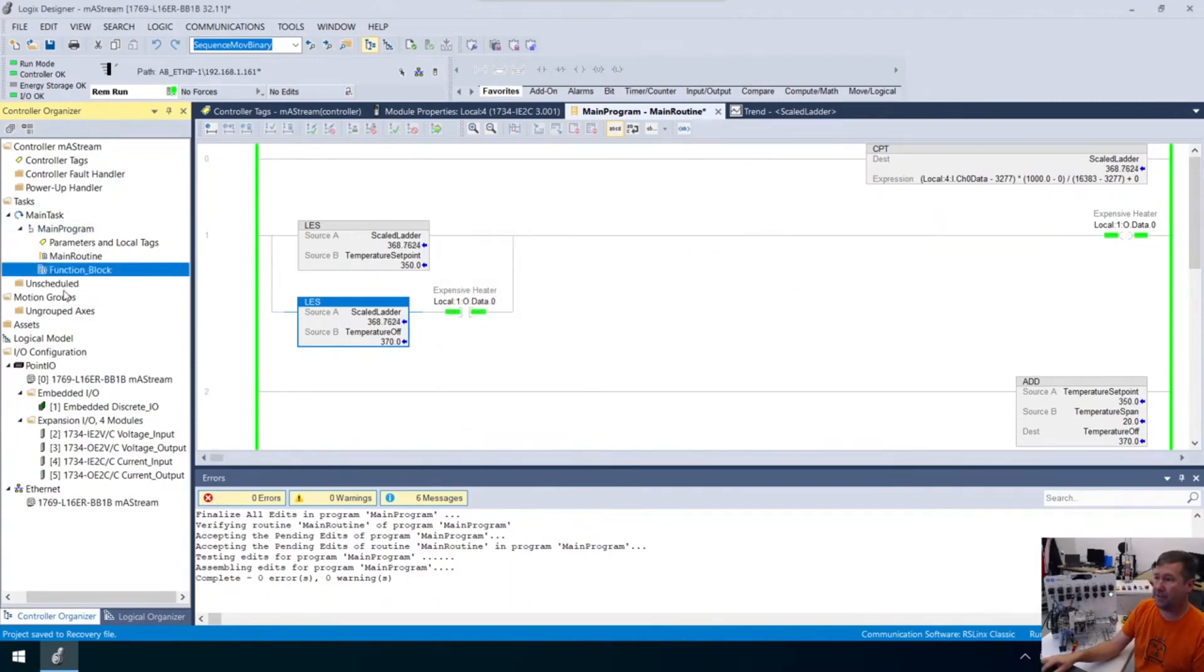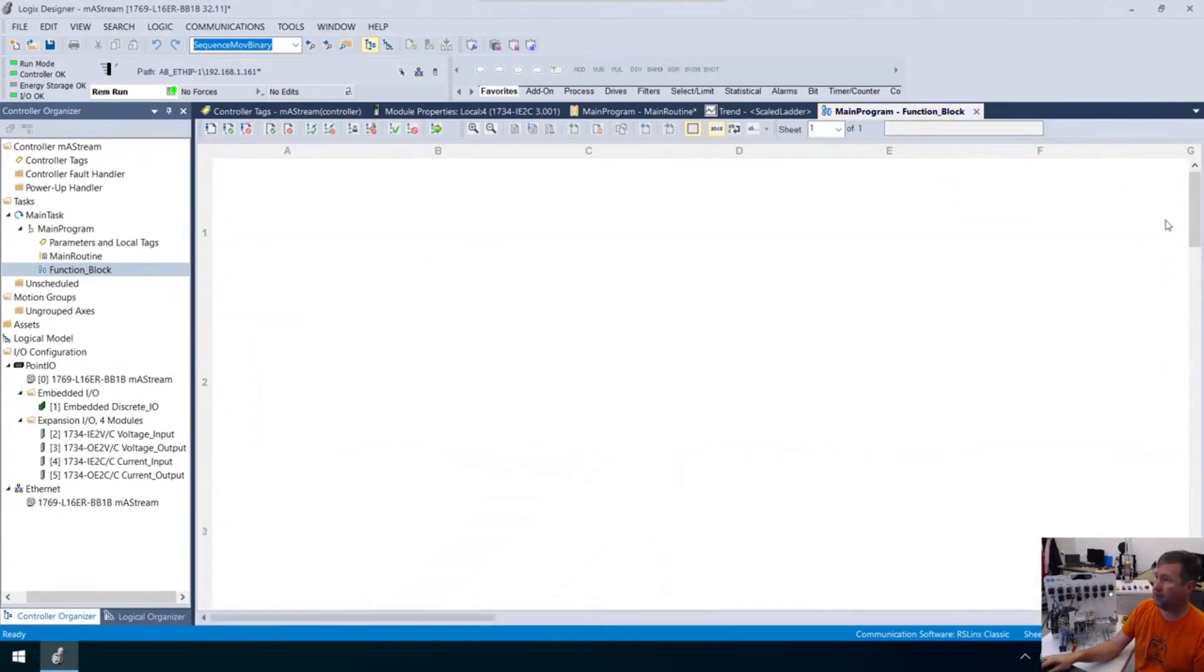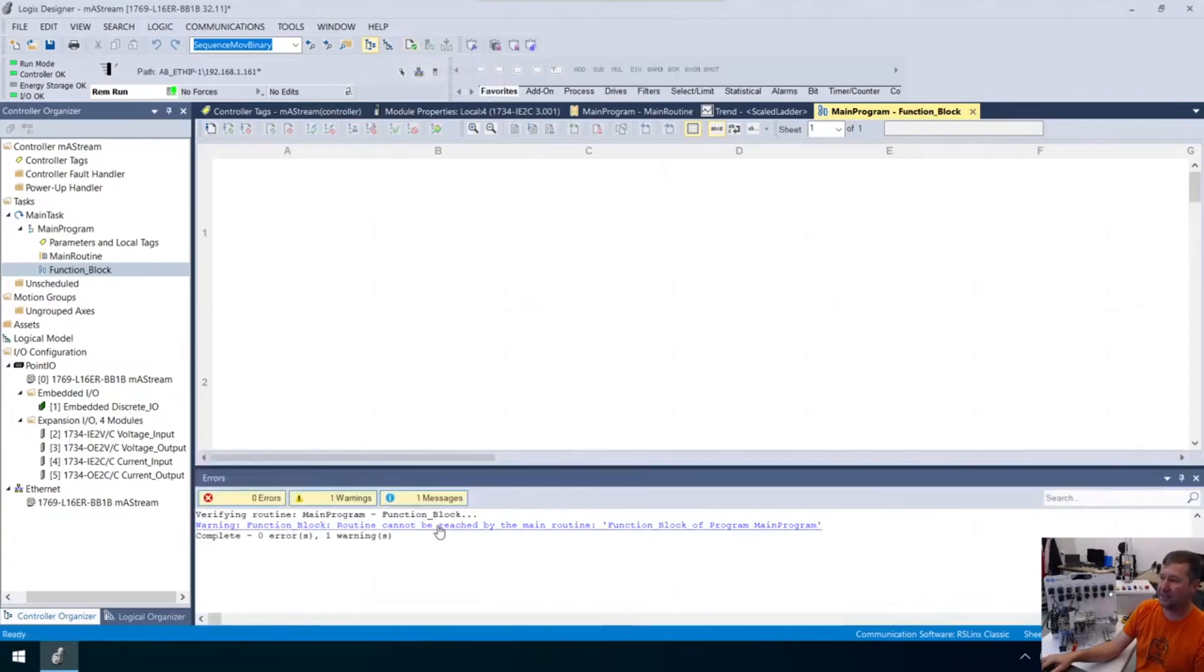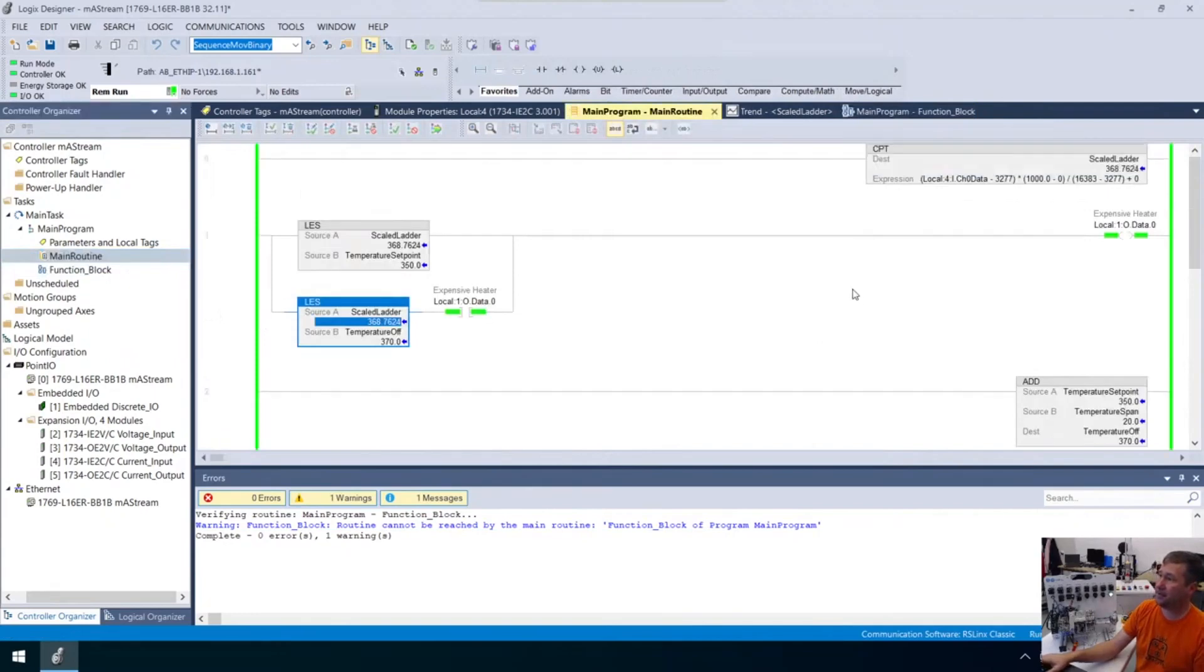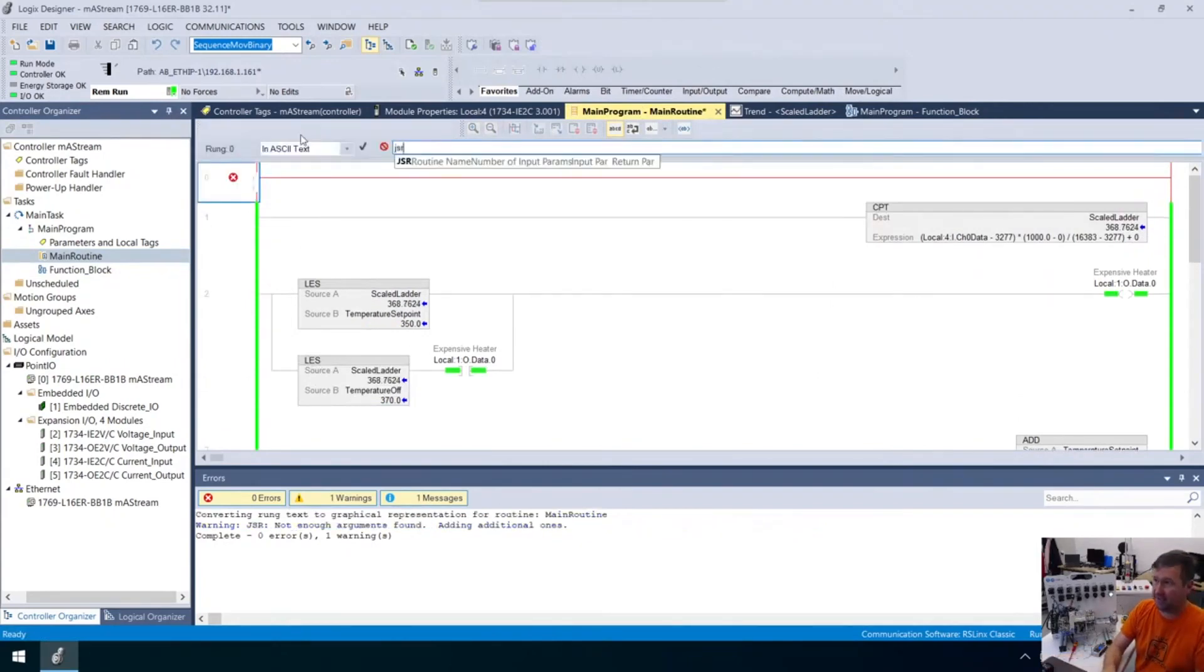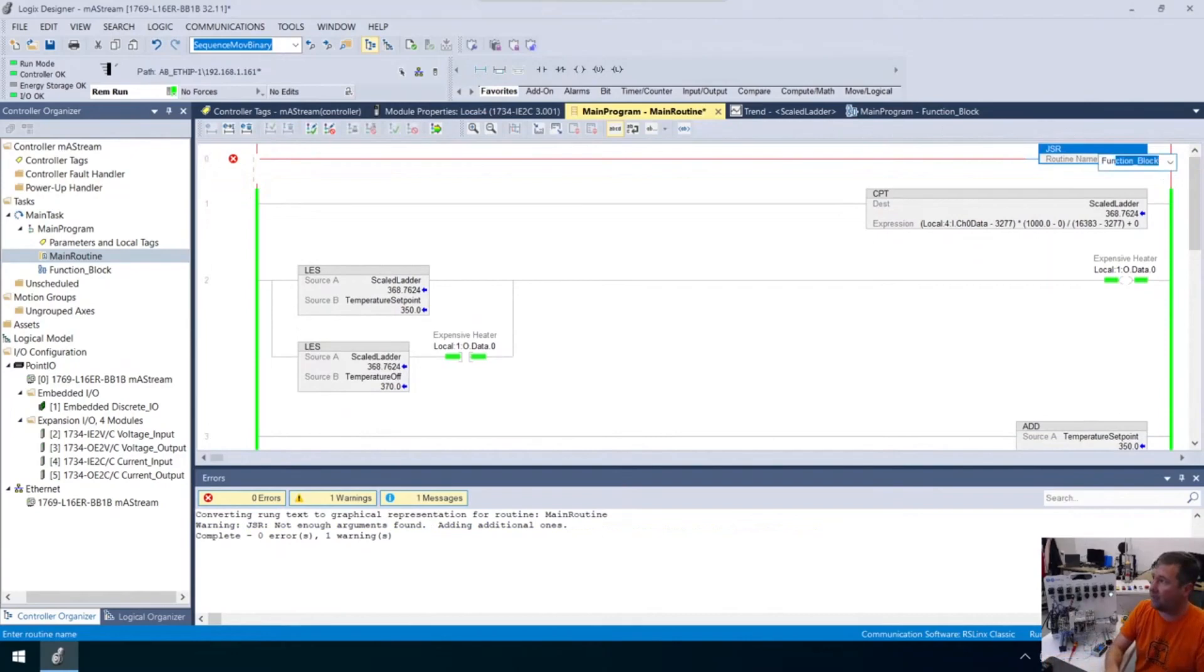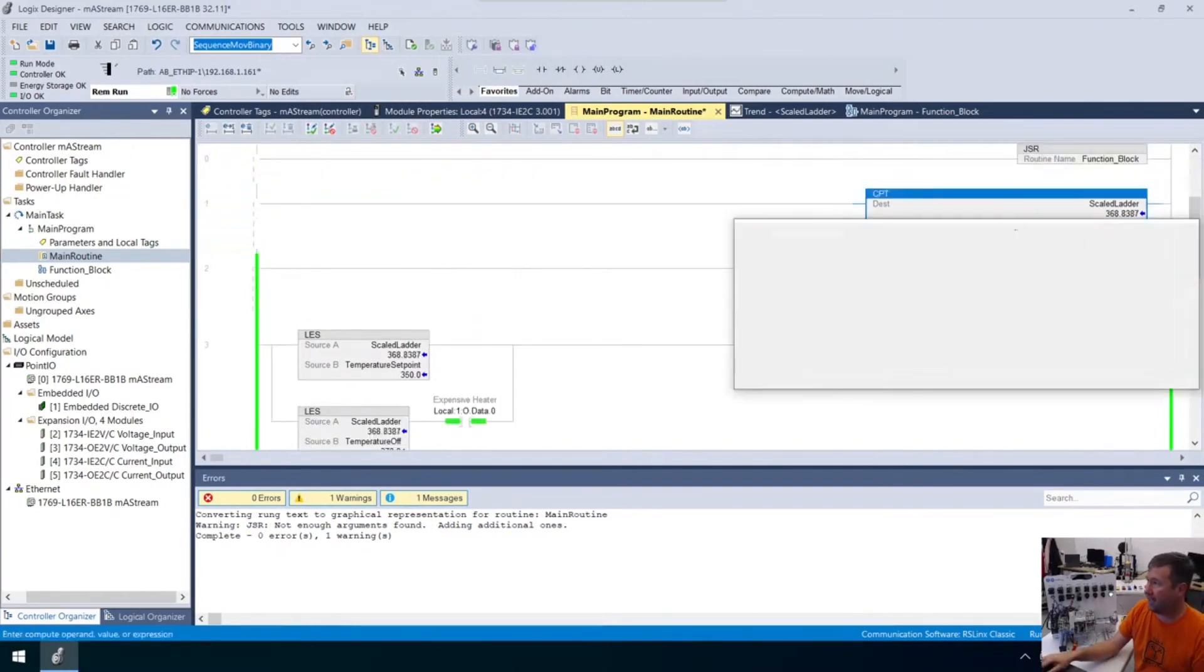Now we've created a new routine. We have no green here, which means there's no possibility of this being scanned. We get a warning: function block routine cannot be reached by main routine. What that means is we need a JSR up here in our main routine. I'm going to add another rung with a JSR to that function block routine. That's going to get that one scanning.